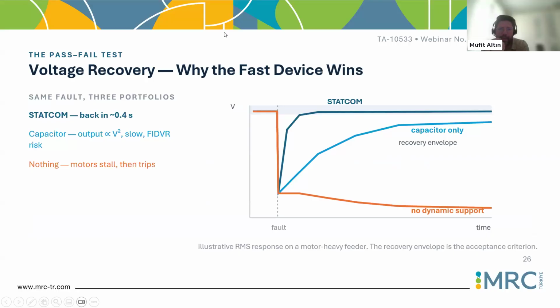So this is what I tried to summarize on the graph. STATCOMs, in less than 5 milliseconds, you can control your voltage and inject current even during the fault. Capacitors, of course, are static. Even if you control them, you need time, and the voltage is important. It correlates with V squared, so how much reactive power you inject depends on V squared. They are slow, and as I mentioned, fault-induced delayed voltage recovery will be there. It will take some time depending on your system.